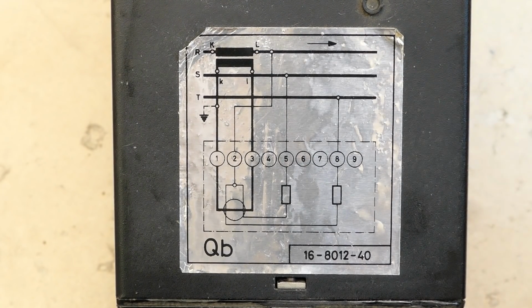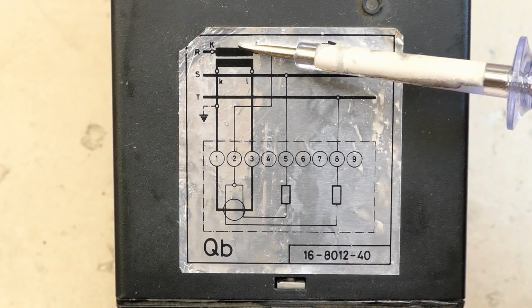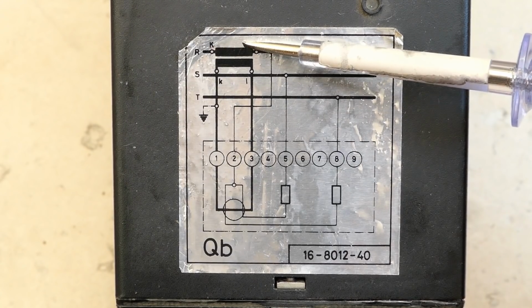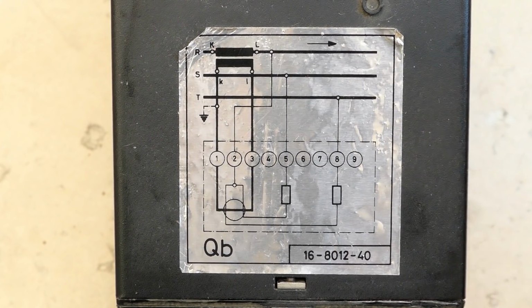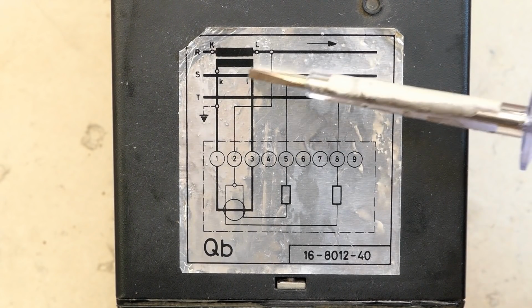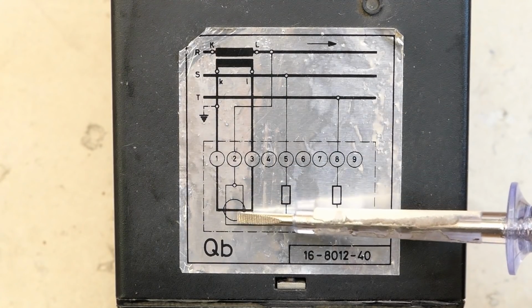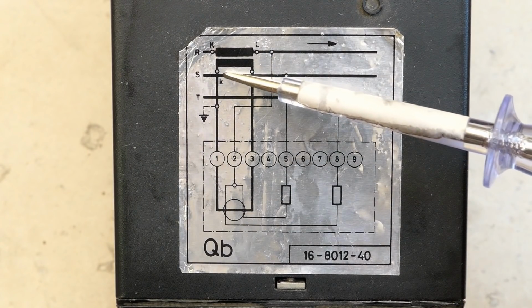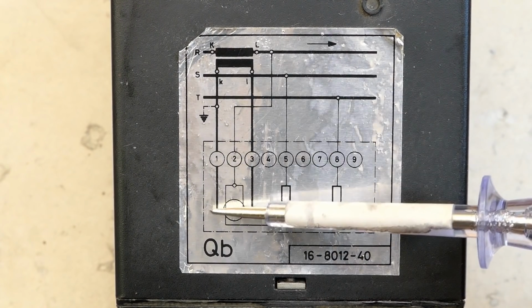turns. And of course transformers transform the voltage in the same ratio as the number of turns, but the current is transformed in the opposite ratio. So having more turns on the secondary steps the current down.